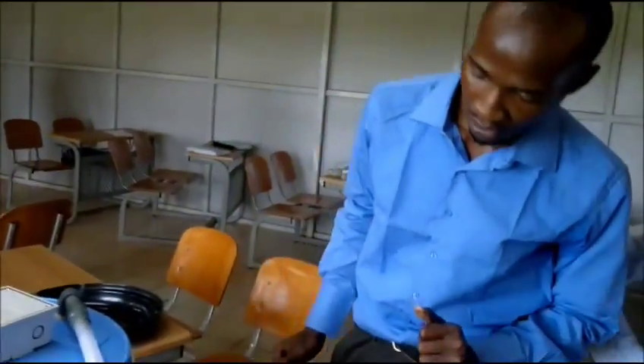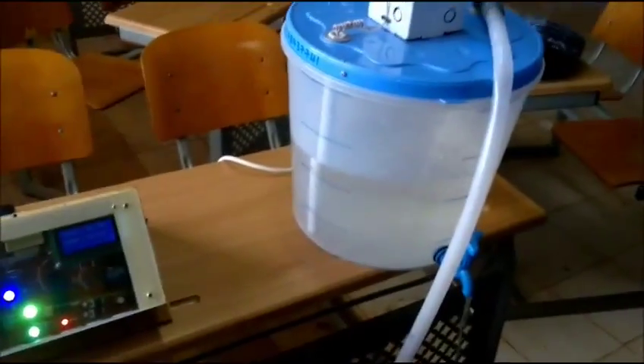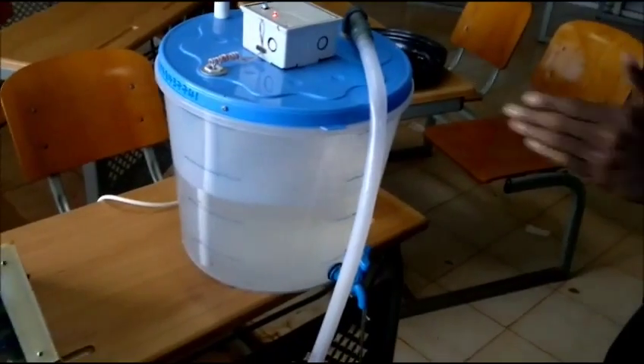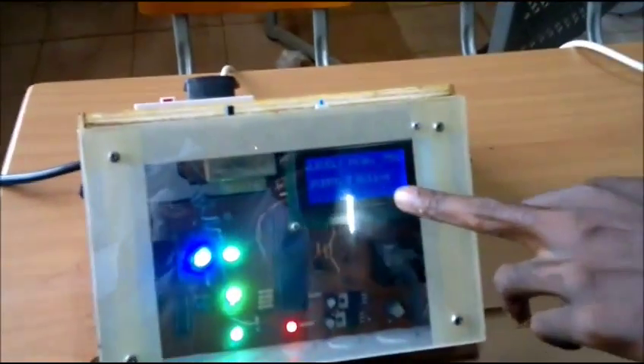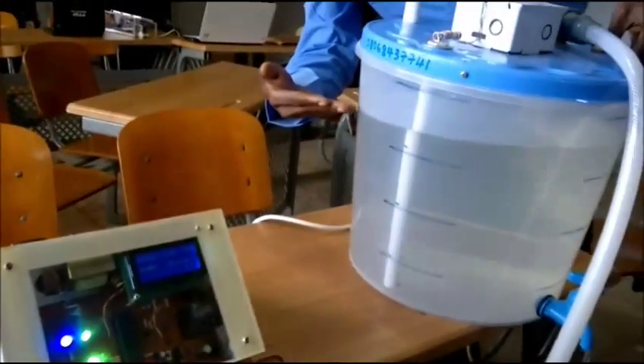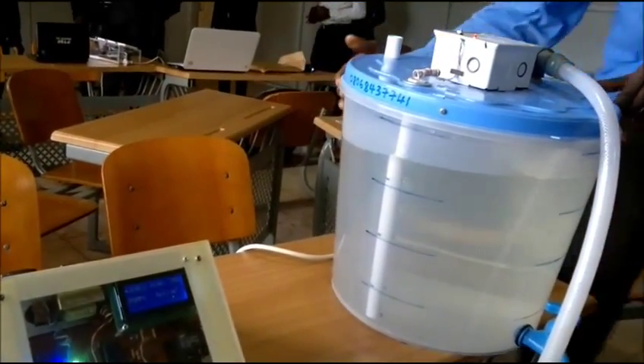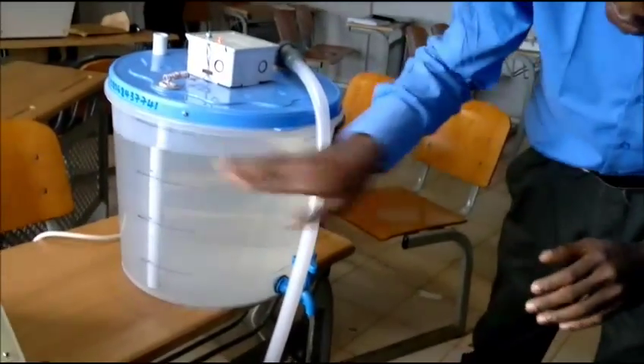As you can see, the pumping has started. When did you want it to start pumping? Because it has a preset value — it started pumping at 25%. The monitor is now at 75%, the pump is acting. And as you can see now, the water level is still rising. It is programmed to stop pumping once it hits 100%.